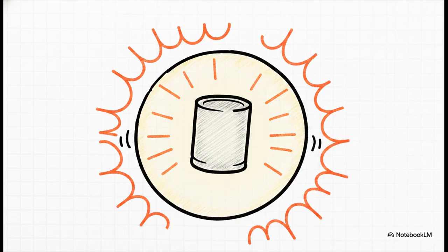Another essential metric you'll spot on elite specs is total harmonic distortion, or THD. High-quality systems must maintain an output THD of less than 3%. Why does this matter? Well, high harmonic distortion generates excessive heat. Keeping that THD under 3% ensures the longevity and physical survival of the highly sensitive capacitors inside your servers and medical devices. Basically, it protects your massive investments from aging prematurely.